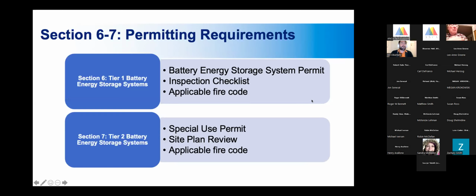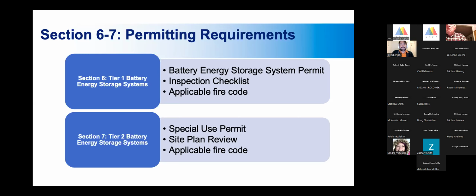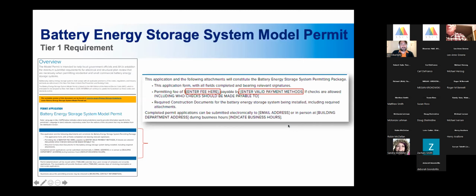Here are the permitting requirements NYSERDA suggests through the model law for the two tiers. For tier 1, NYSERDA suggests adopting the battery energy storage system permit and inspection checklist so these systems can be permitted through your building department, along with strongly advising application of the fire code as state law. For tier 2 systems, over 600 kilowatt hours, you move into a special use permit and site plan review process, with the fire code still applying. So you see the more traditional land use regulation tools coming out for tier 2 systems.